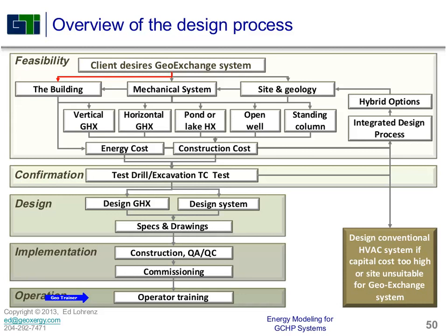I think basically, you can model that in GLD by manually changing the borehole thermal resistance of the U-tube. That's probably the best way to do that.